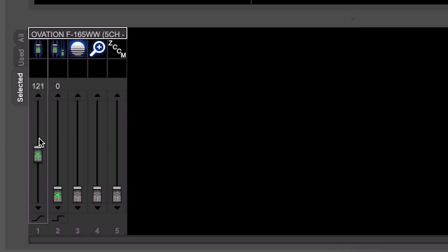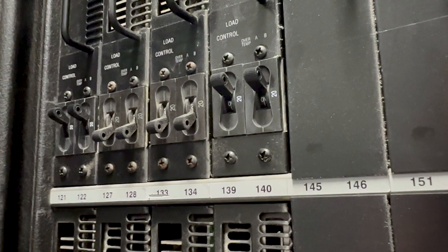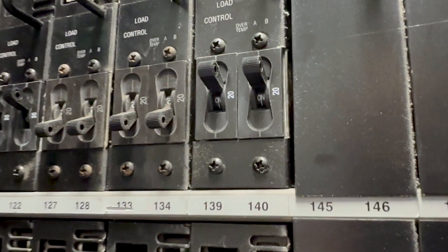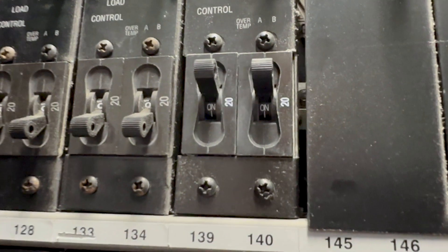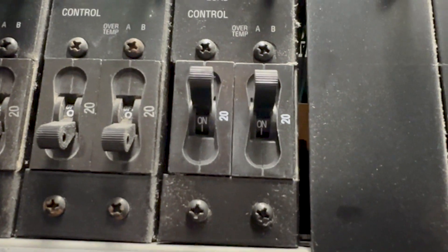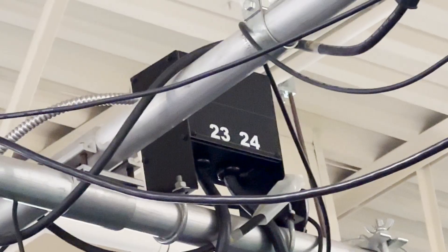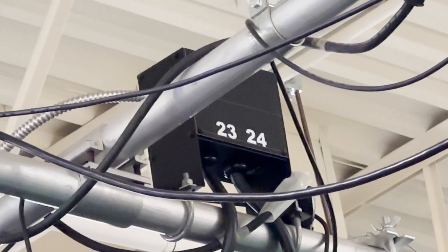You may even have some non-dim modules that you need to energize by sending a command in order to power your lights, so make sure those are always on for each scene when programming too, or else your lights won't light.